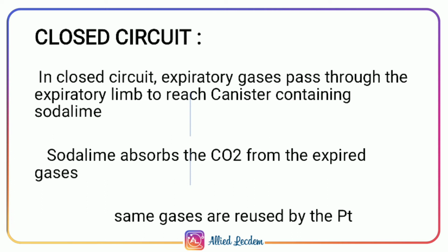During inspiration and expiration, the system is closed, so the patient has to breathe the same anesthetic mixture again and again. The soda lime present in this system absorbs the CO2 exhaled by the patient, and so there is no accumulation of CO2. This method is most commonly used nowadays.